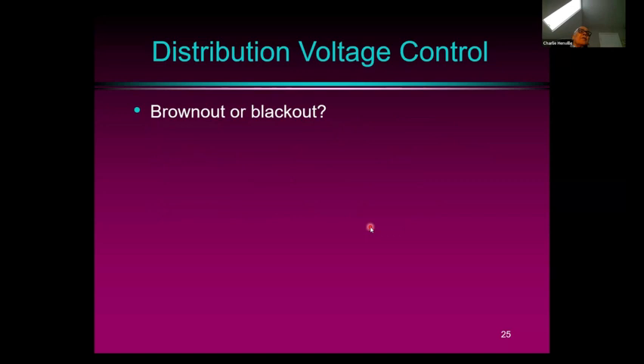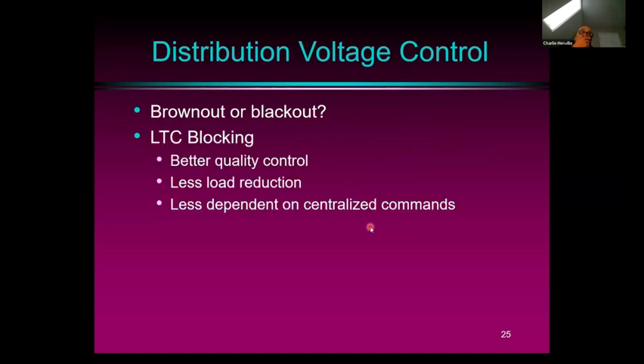One method of controlling the voltage is just to control the distribution voltage. So allow the voltage to go down, but only to a certain level. And here you have to decide whether you're going to have a brownout or a blackout, because if you reduce the voltage too much, then you'll have a brownout, and if you don't reduce it enough, you might have a blackout. So some ways of reducing the voltage are blocking load tap changers, for instance, and you get better quality control there, but not so much load reduction if you don't allow the load tap changer to move to its full extent. And so usually if you're using load tap changer blocking, you don't need as much centralized command to tell it to be blocked.